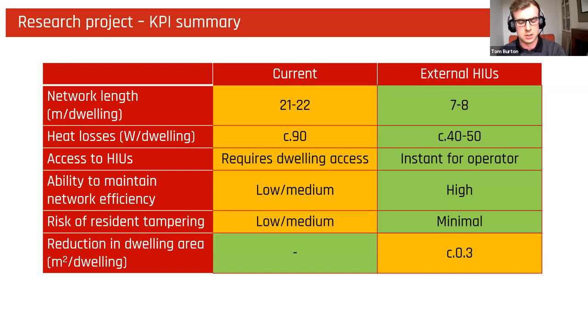So before we get into the results, just a few key outcomes of the research. From a network length perspective, external HIUs allow you to reduce your network length by about 65%, which is absolutely massive, and has a large impact from a capex perspective. From a heat loss perspective, you go from around 90 watts per dwelling, which is really on the boundary of the CP1 2020 boundary, down to 40, 50 watts per dwelling, perhaps even lower, which means you're very comfortably below that. This is also going to have quite a big impact on reducing heat tariff and making sure that your heat is affordable for your residents.